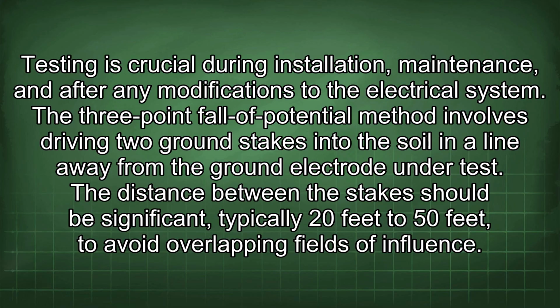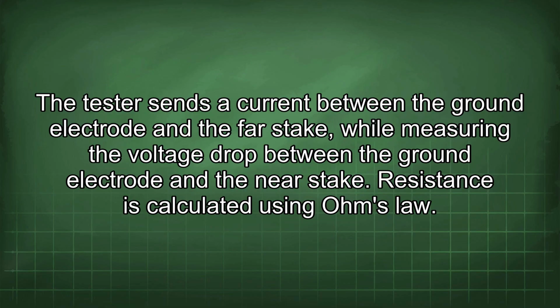The three-point fall of potential method involves driving 2 ground stakes into the soil in a line away from the ground electrode under test. The distance between the stakes should be significant, typically 20 feet to 50 feet, to avoid overlapping fields of influence. The tester sends a current between the ground electrode and the far stake, while measuring the voltage drop between the ground electrode and the near stake. Resistance is calculated using Ohm's law.